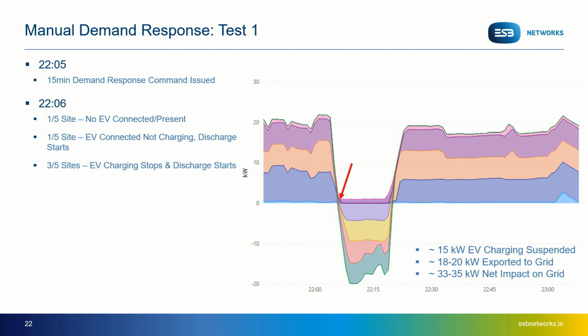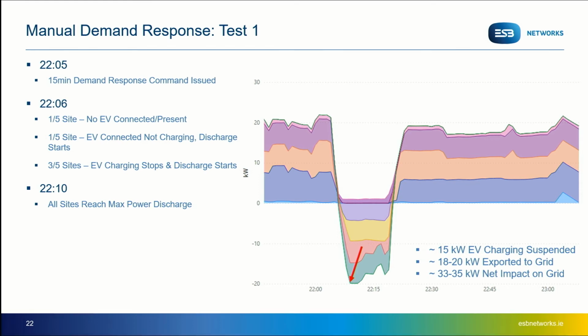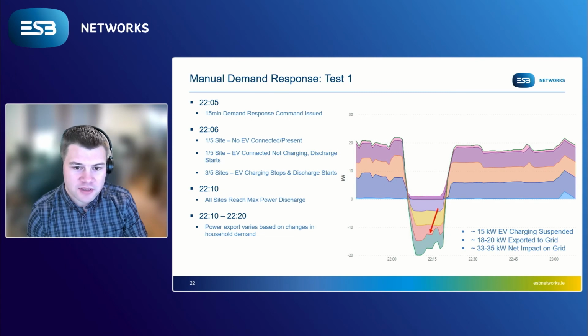By 22:06, a number of sites had started to respond. Those 3 sites which were charging stopped charging and started to discharge. Another site which had an EV connected but wasn't charging also started to discharge. The 5th site offered no response as there was either no EV there or it wasn't connected at the time. By 22:10, the discharge from each of the vehicle to grid chargers had ramped up to its max output, with each of the 4 participating sites exporting approximately 5.5 kilowatts, with the combined net export to the grid of around 20 kilowatts. Between 22:10 and 22:20, we can see the combined export vary as the household consumption varies at one site, that represented in the red color.